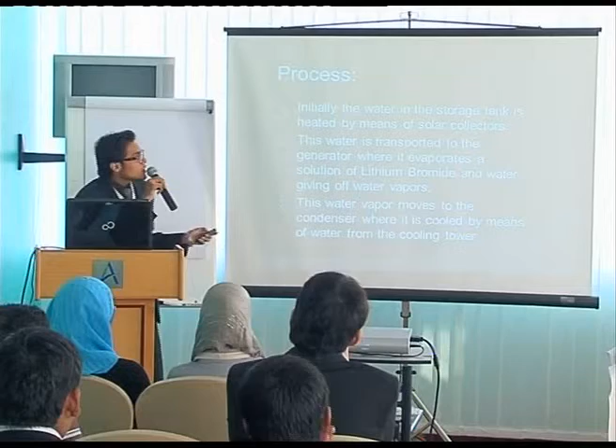Now we'll break the system into a step-by-step explanation, starting with the collectors. The collectors we've proposed are flat plate collectors, featuring double glazing and insulation so they can withstand temperatures up to 93 degrees Celsius, or 200 degrees Fahrenheit. The working fluid used here is a lithium bromide solution. According to the book by P.J. Wilbur and D.S. Word, studies have shown that using lithium bromide as the working fluid gives better efficiency and better COP than other working fluid models in solar absorption systems. That's the first process.